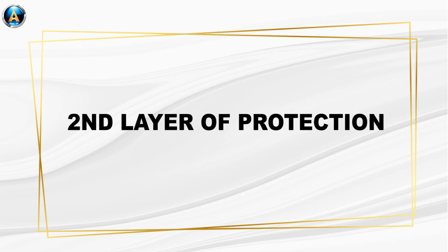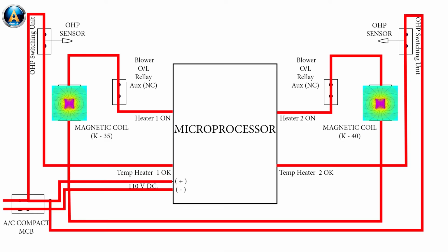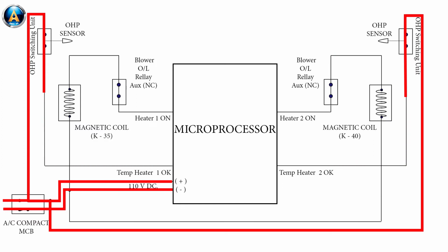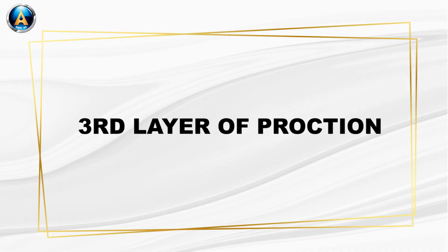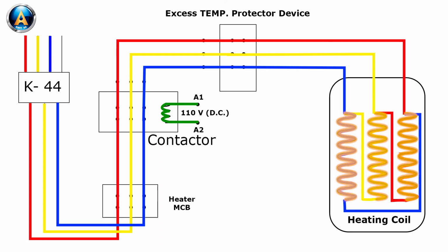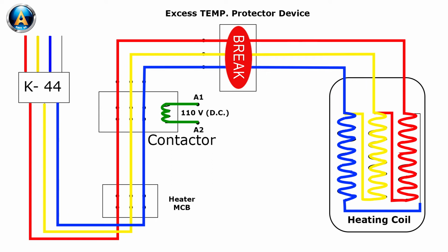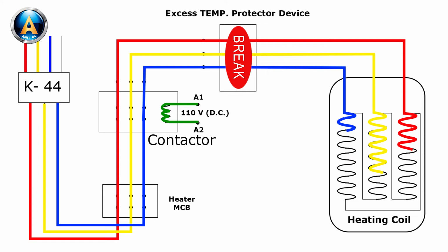The second layer of protection barrier is controlled by the OHP device, because whenever the air temperature near the heating coil reaches above 65 degrees centigrade, then the heating coil becomes inactive by the OHP device, like this. The third layer of protection barrier is controlled by the excess temperature protector device with STI cartridge, because whenever the air temperature near the heating coil reaches 130 degrees centigrade, then the heating coil becomes inactive by the STI cartridge.